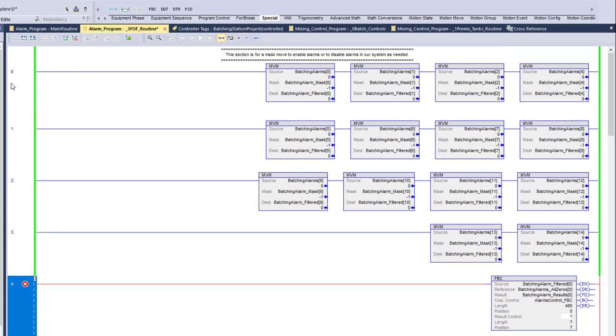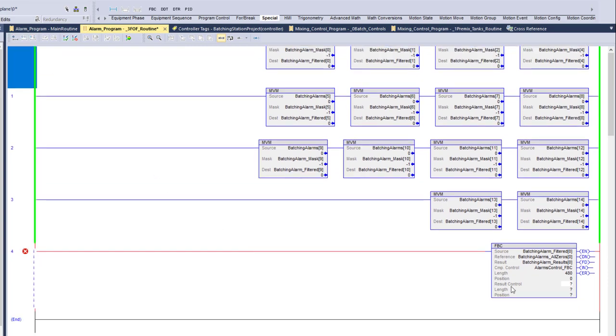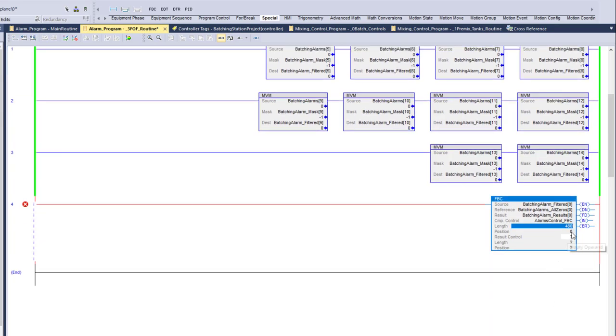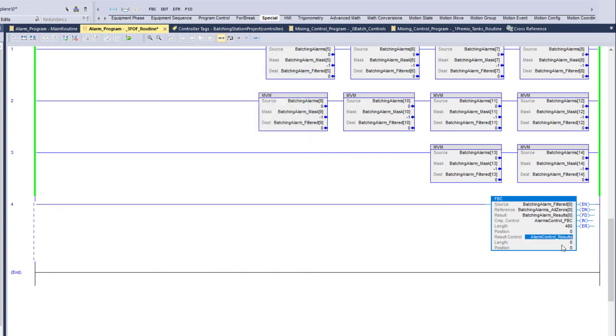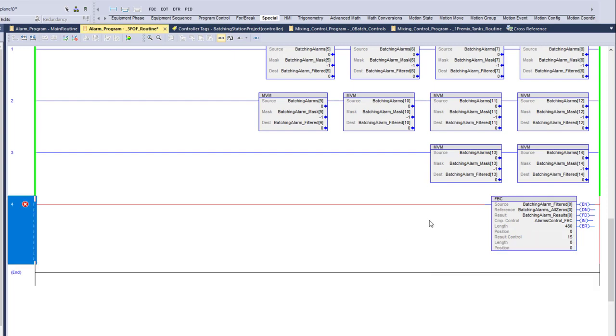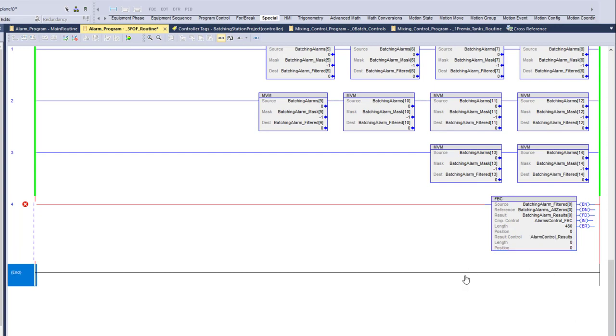In the instance of our first rung it was only 120 bits, so we would have just put 120 bits — it's that simple. The position is where it will end up when it finds a difference. We also need to add a result control — we'll call this 'alarm control result' as a standard tag. Then give it a length of 15. Make sure the controls are entered correctly — a good indicator is whether your rung edits show as valid on the left-hand side.